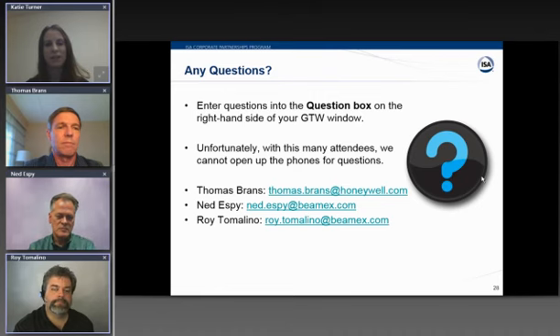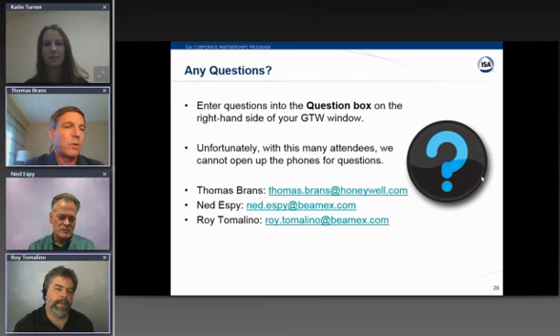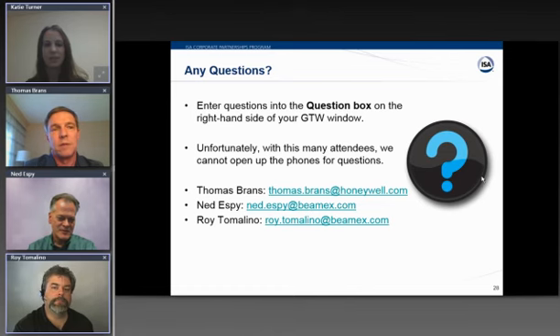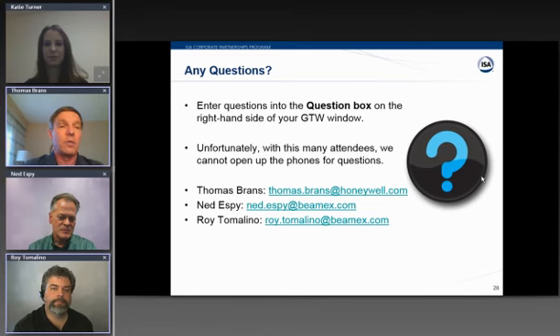Okay, next question. What will be the difference on calibrating or ranging a temperature instrument? I'm sorry, can you repeat that one, Katie? The question is, what will be the difference on calibrating or ranging a temperature instrument? Okay, I can answer that if you want. So I always think of it this way, is calibrating is comparing an instrument to a known standard. So typically what you'll do is go up and check out an instrument, and when you check it out, you're comparing its output to a standard that you're assuming is the right reading, and if your temperature instrument is close enough to the standard, then no change is necessary. But if you go to check that instrument and it's out of tolerance compared to that standard, then you have to calibrate it. And in simple terms, the calibration means forcing that instrument to agree with that standard.